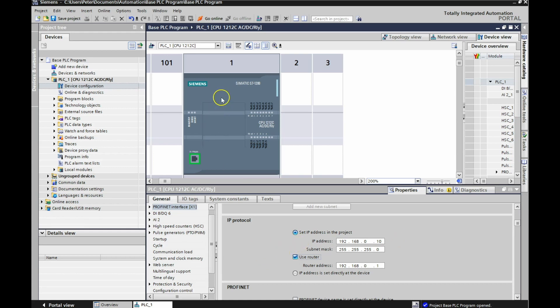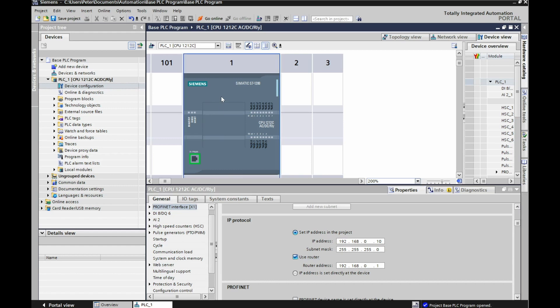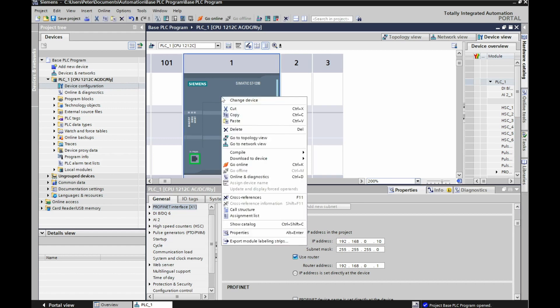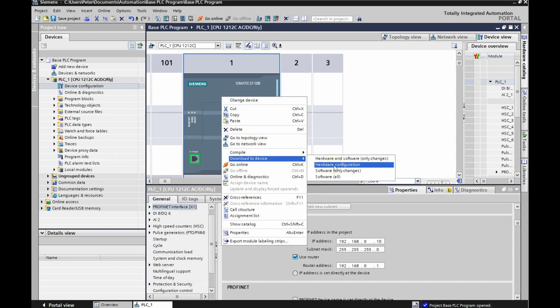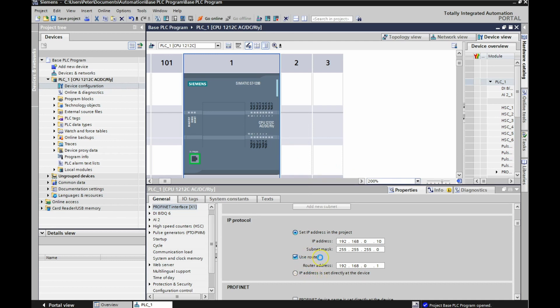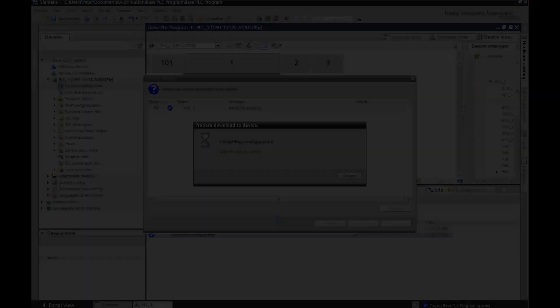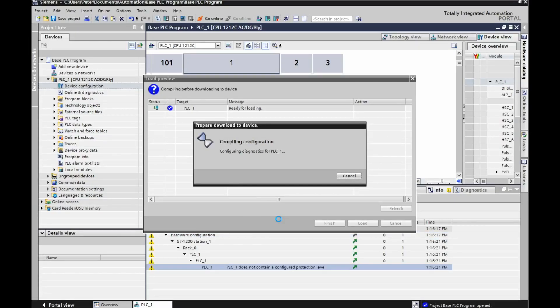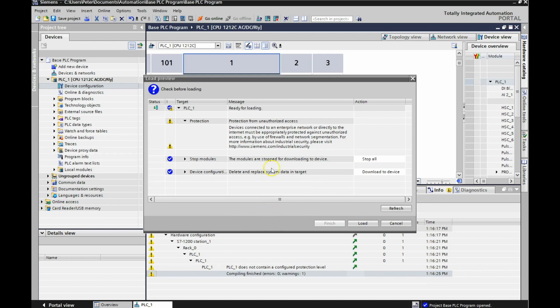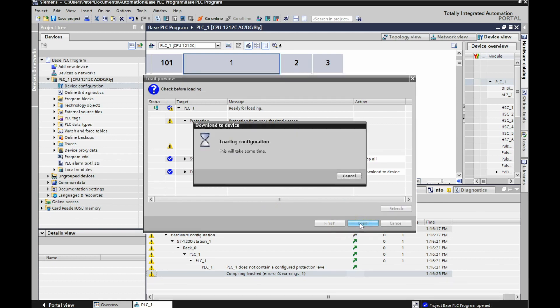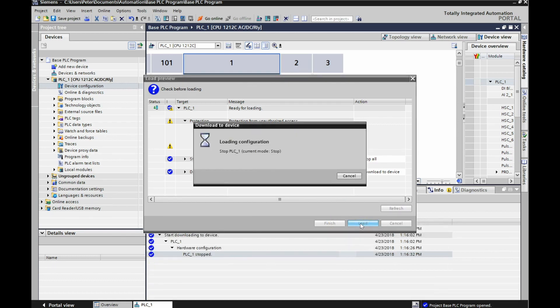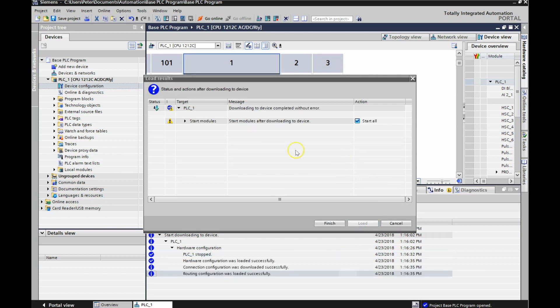Once you've done that, come up here and go back to the PLC. Right-click on the PLC, go down to 'download to device,' and we're going to download the hardware configuration. This is if you haven't already done the changes to use the router to talk to your PLC. It looks like it's already done the search — you may have to search for the PLC and then hit load. Hit load, and when the next window comes up, select 'start all' and then finish.